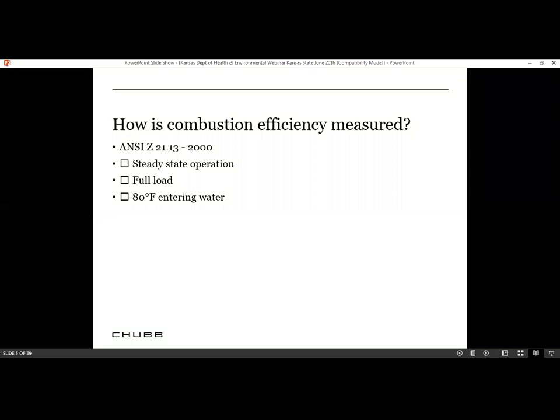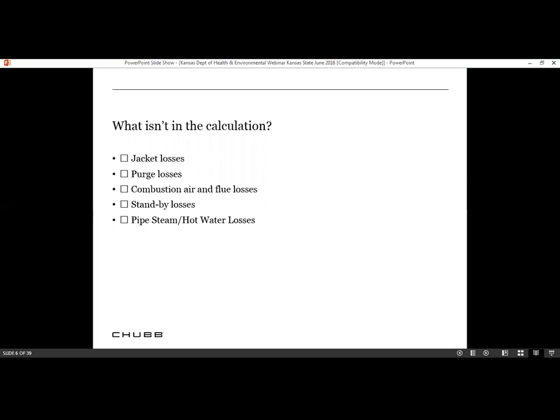How is combustion efficiency measured? If you go to ANSI Z21.13, 2000 edition, it talks about steady state operation, full load operation, and we look at a temperature of 80 degrees entering water. What isn't in the calculation, however, is probably where we as a user could actually influence that, and that's jacket losses, purge losses, combustion air and flue gas losses, standby losses, and pipe, steam, and hot water losses.